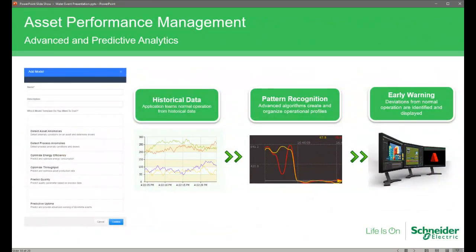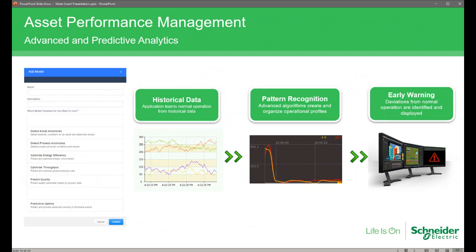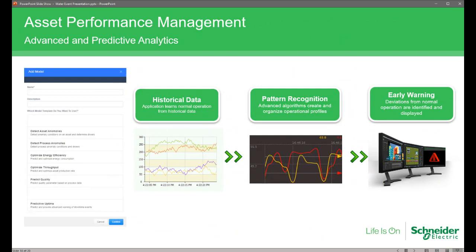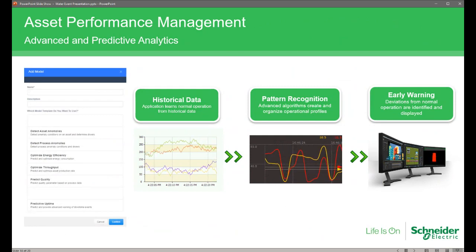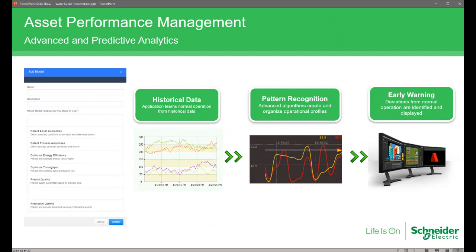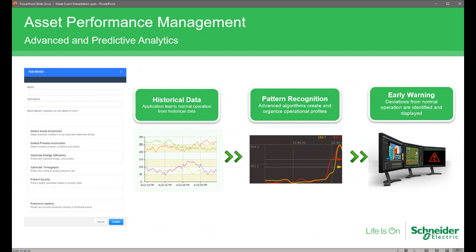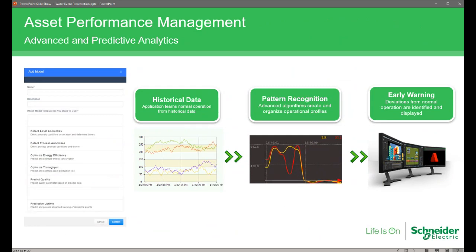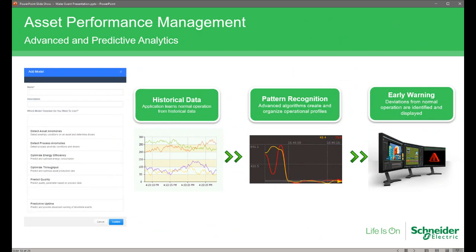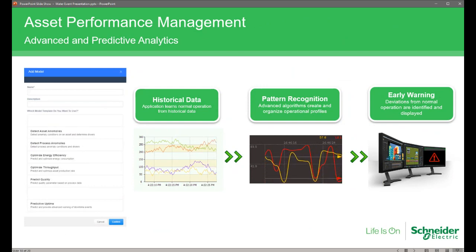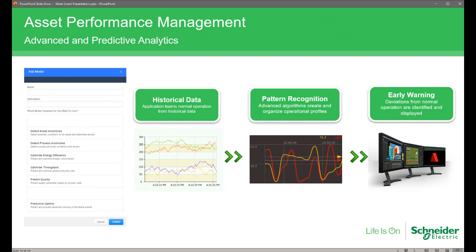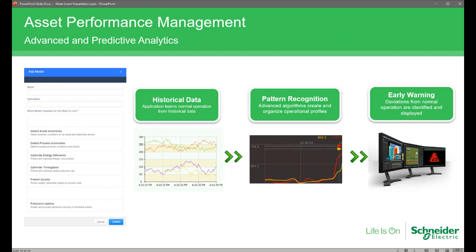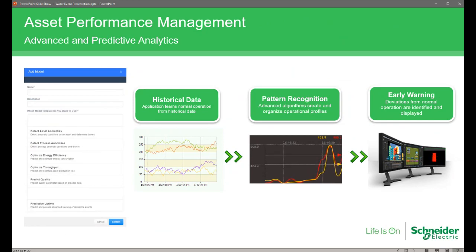Advanced analytics is targeted towards assets and processes that are complex or considered extremely critical. This allows models to be created by selecting tags, just like guided. However, a user is able to tune the model or select the model type to focus on a specific area — be it to reduce downtime, increase asset reliability, help maintain quality, or look at useful remaining life. Think of advanced as more about predicting quality and predicting failure, whereas guided is more about anomaly detection. Advanced analytics gives the ability to define models deployed to ensure they are fit for purpose. There's still no need to be a data scientist, but tuning the model may be required depending on the solution chosen.